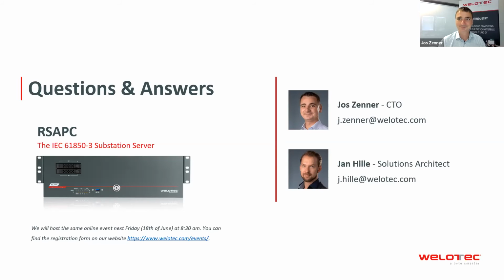I'll take that. Okay. So there are in general two possibilities. One possibility is that you run a software that supports PRP. HSR is a little bit complex, but we do it with hardware support. So we have extension cards that we can put in. We have the possibility of up to 8 interfaces, so it would be 4 redundant networks that we can connect at the same time. And those cards are using FPGA, which is very fast and accurate.